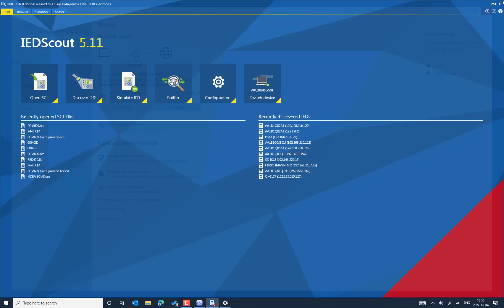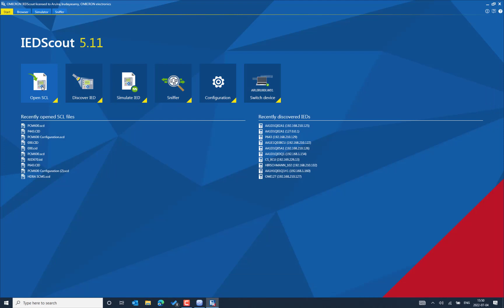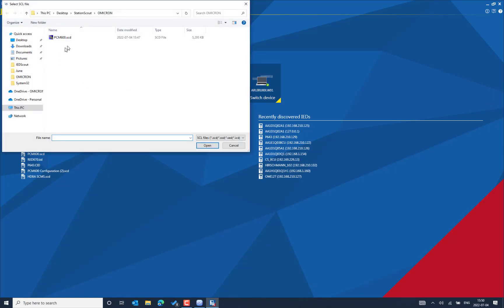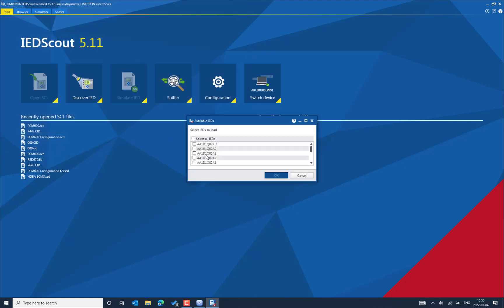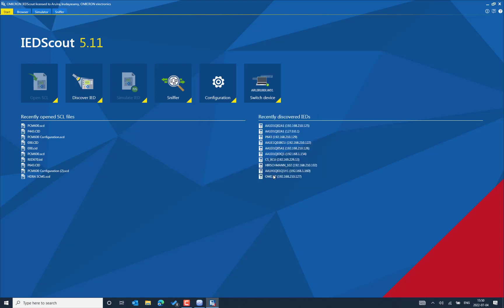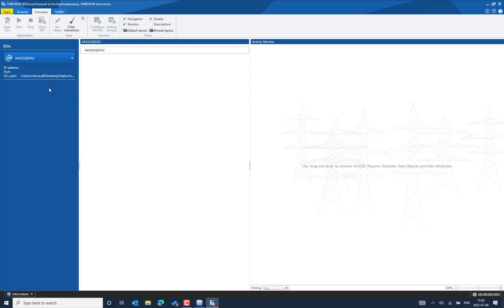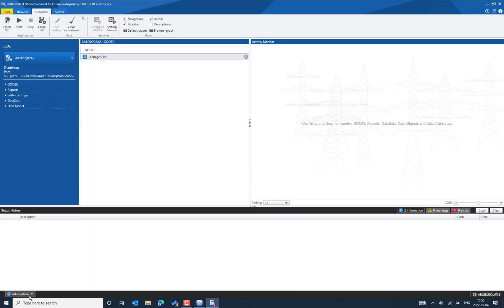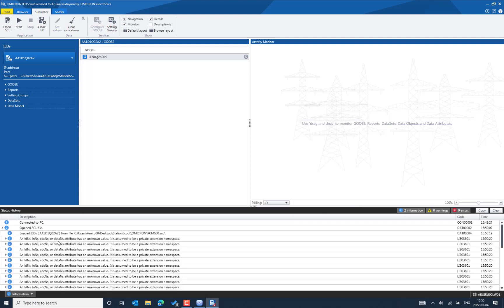Let's close the interface, then select the Simulate IED option and provide the input as an SCD file. We can pick all the information or the specific IED we want to simulate. The SCL file is being imported into the simulator section. The SCL content has been loaded and we can see the information. There are some private extensions noted, but that is not a big problem. Then we can start the IED simulation.